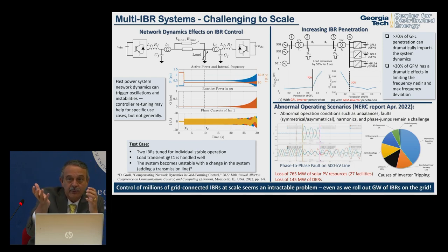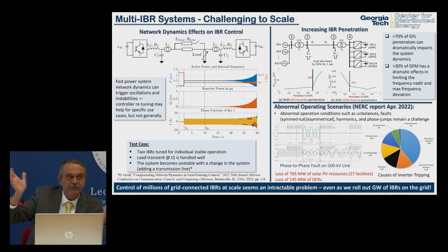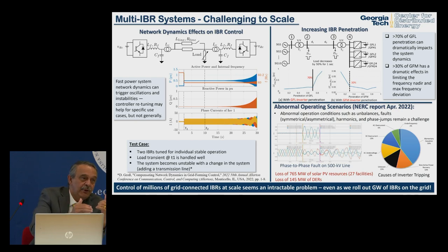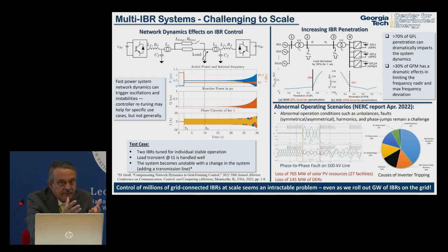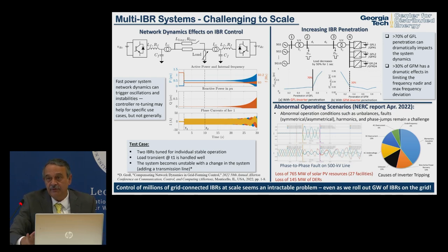Grid-forming inverters: once you lose synchronous generators, inverters need grid-forming capability. Many companies claim they have it, but there's no good definition. What is clear is that if you only have grid-following inverters, as penetration level increases the system goes unstable. Some IBR penetration with grid-forming capability is needed, but these things are not well understood. Millions of grid-connected inverters: controlling them at scale seems an intractable problem, but that's not stopping us from rolling out gigawatts.